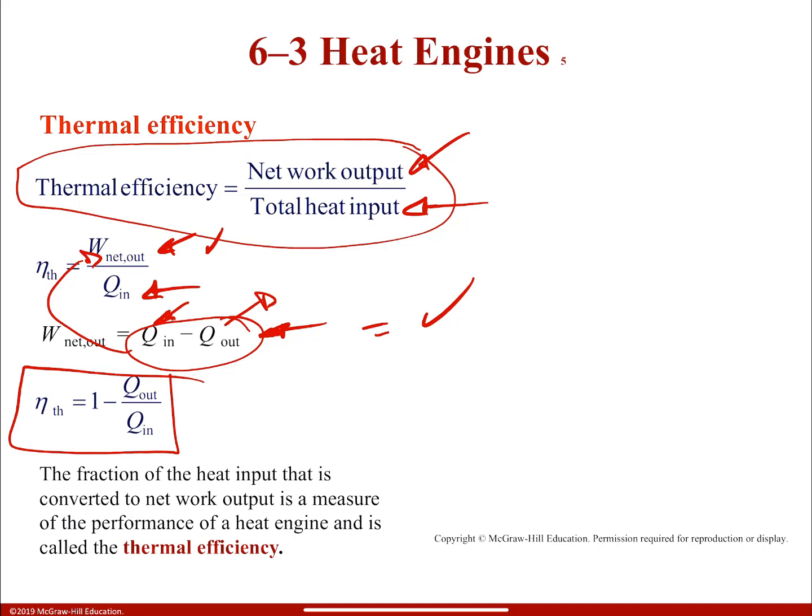And then they asked, okay, how high is the temperature of the room where the compressors are being held? The temperature was a lot higher than in Germany. And they said, yeah, that's right, that's why. Because in Germany we have one environment and you have a different environment in Venezuela, and that's why the compressors are not performing in the right way. So we're talking about like $2 million of equipment. They were studying if it was worthwhile to make a room only for the compressors and then put some AC or something like that in order to reach that temperature.